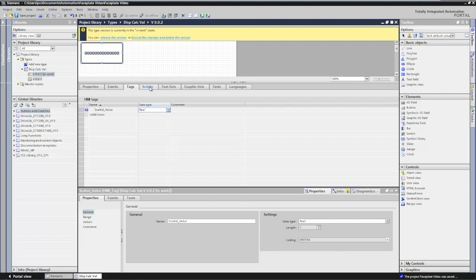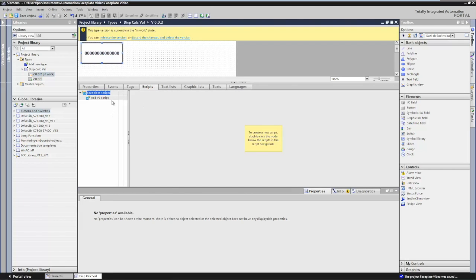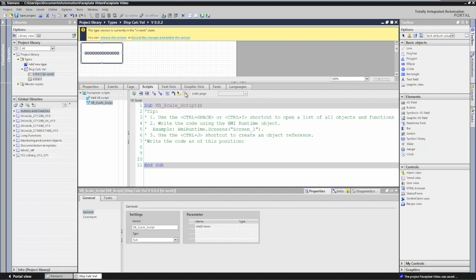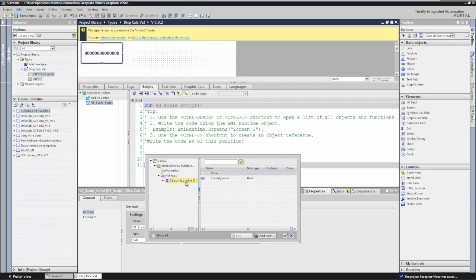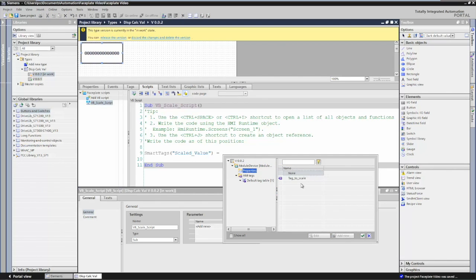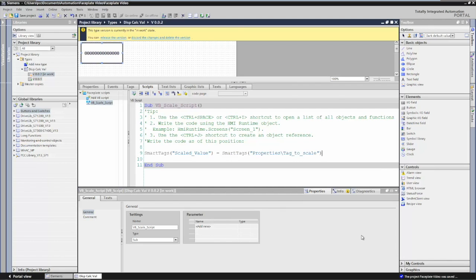The next thing I'll do is move over to the scripts tab and add a script. I'll change the name of the script and call it vb_scale_script. This is the script we're going to use to put our code to scale the value. In the script editor, I'll go up to the toolbar and select List Objects — now I can browse for my faceplate tags or faceplate properties. I'll select the scaled value, which inserts the SmartTags function, put in an equal sign as an assignment, and then select the tag_to_scale property, which will ultimately be the tag we pass in.